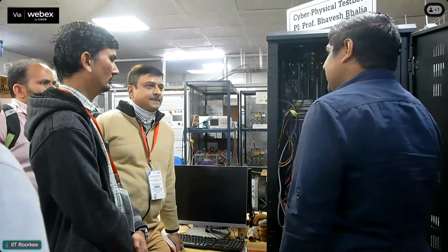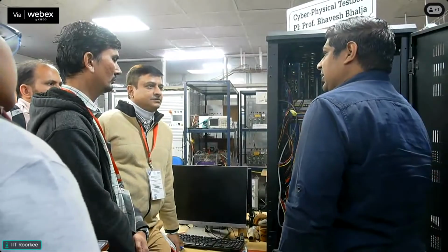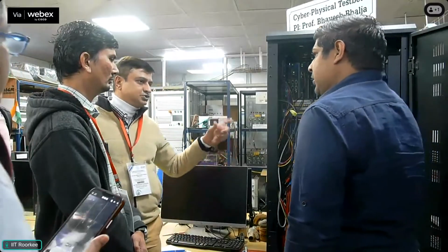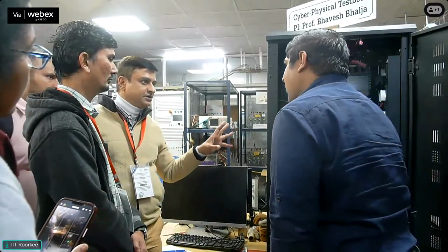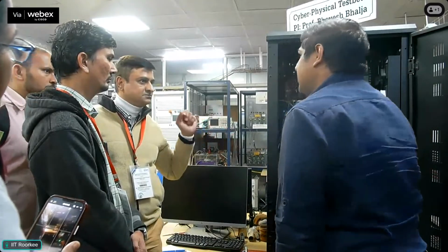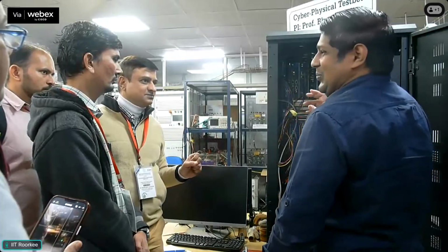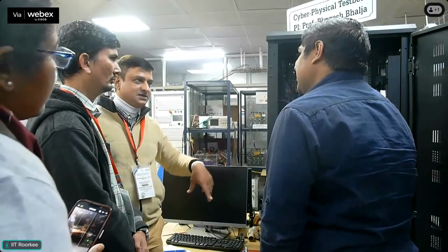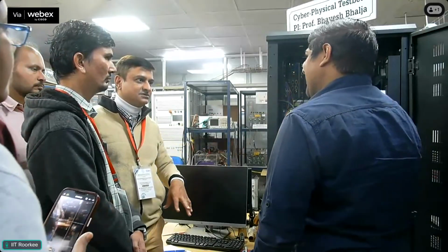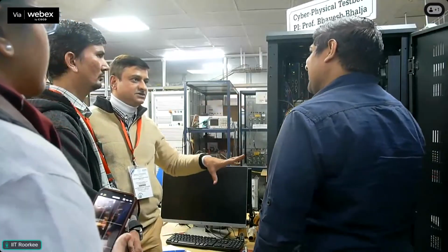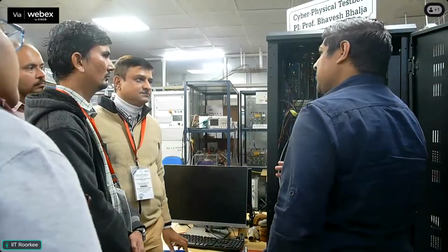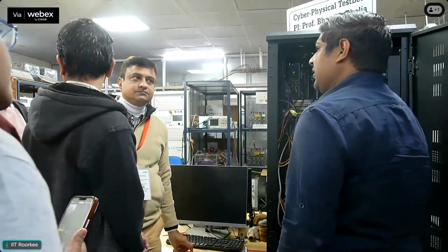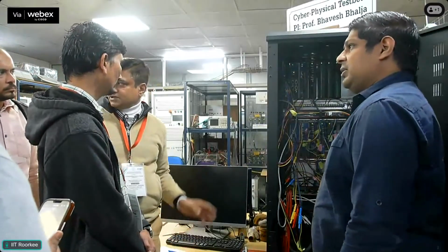But mostly in the PDC we can receive only 8 at least. Yeah, that is the PDC capacity. Can virtual PMUs be configured as any make? It is not make specific. The virtual PMU is from RSCAD. It doesn't ask for any make, it gives the same feature. It works just as a PMU. It is calculating the phasors and getting time stamped by the GPS clock, and then sending the phasor values.